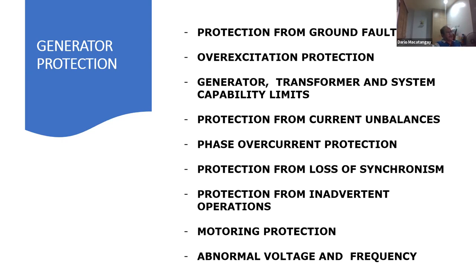Okay, so that is for the overcurrent protection. That needs to be considered when you're protecting a generator. The current decays from a very high value to a smaller value, and there is a time constant associated with it. It's transient in nature.